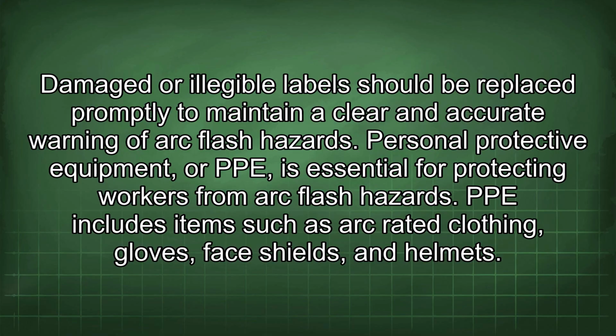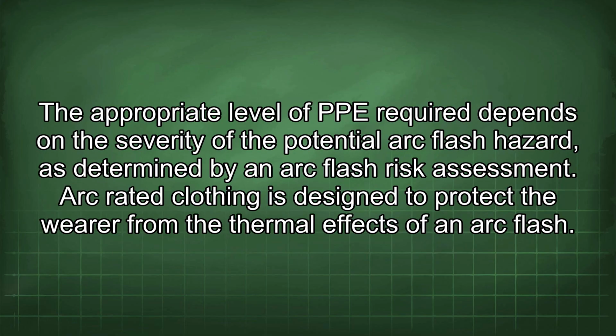Personal protective equipment, or PPE, is essential for protecting workers from arc flash hazards. PPE includes items such as arc-rated clothing, gloves, face shields, and helmets. The appropriate level of PPE required depends on the severity of the potential arc flash hazard, as determined by an arc flash risk assessment. Arc-rated clothing is designed to protect the wearer from the thermal effects of an arc flash.